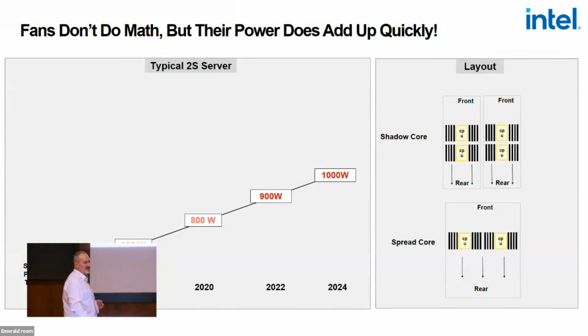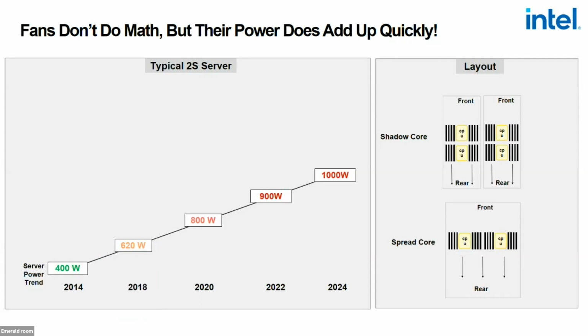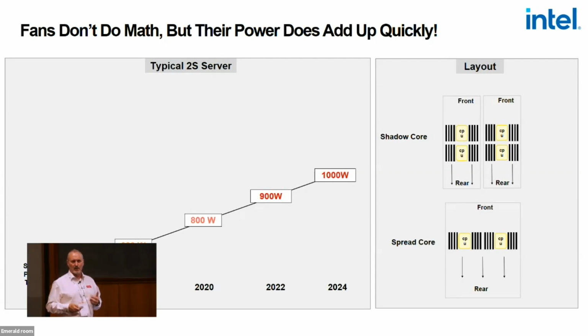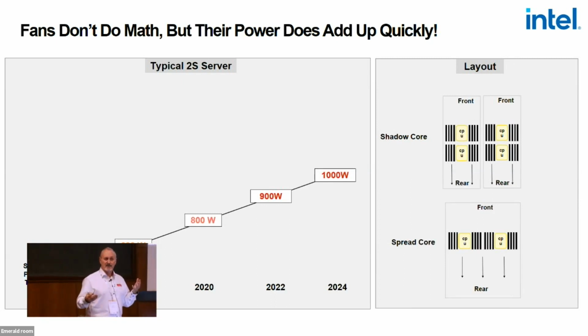Now, fans — don't underestimate their impact. Imagine this picture, then imagine a direct water-cooled environment with no fans, where even your PSUs are direct water-cooled with a heat transfer efficiency of 98%. So 98% of the heat generated by your IT equipment is transferred to water, leaving 2% that isn't — that's called radiation. If you're cooling with water at 50 degrees Celsius, the metal in the infrastructure gets warm and radiates, so that remaining 2% is addressed through other means besides the direct water cooling itself.